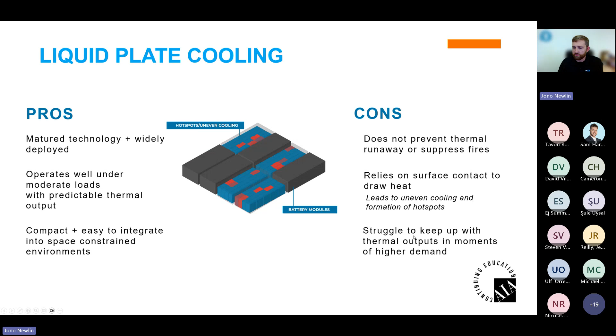So this has been the cause in multiple fires, because you have a malfunction and a leak of the glycol that's running through here. That is one of the main cons for sure, and it relies on surface contact to draw heat. So it needs surface contact. Obviously, for thermal management, that is better than just air blowing, but it does not have the best efficiency drawing heat off of this, and it struggles to keep up with thermal outputs in moments of high demand.